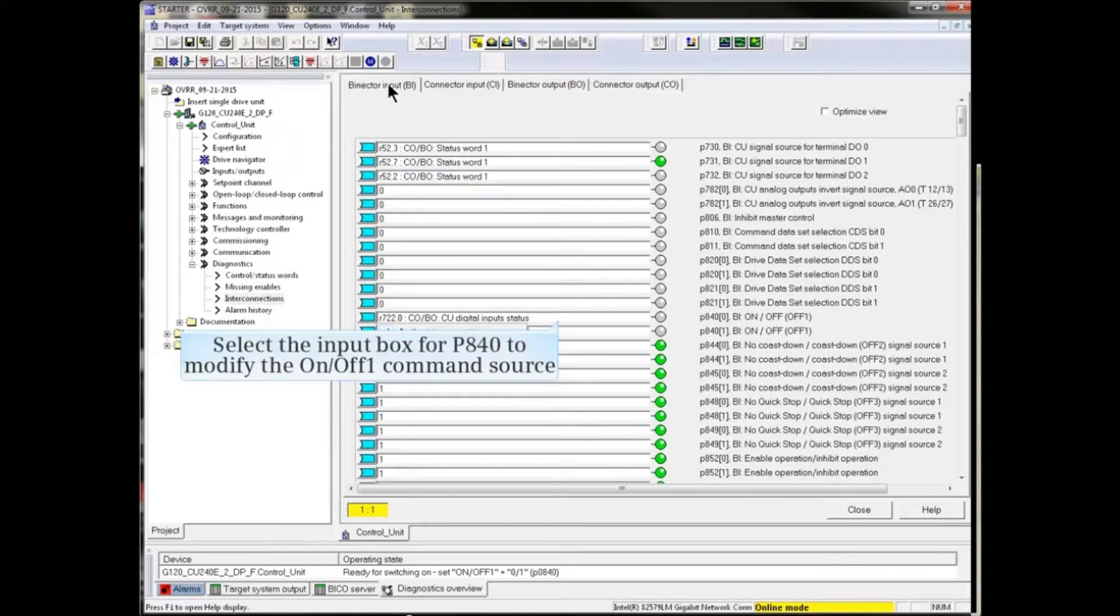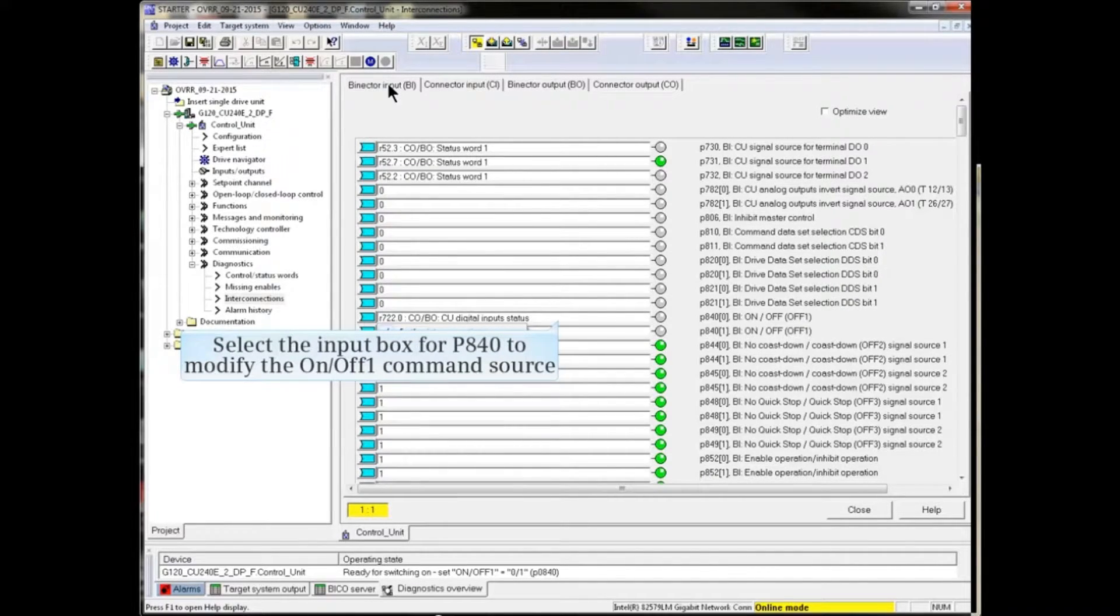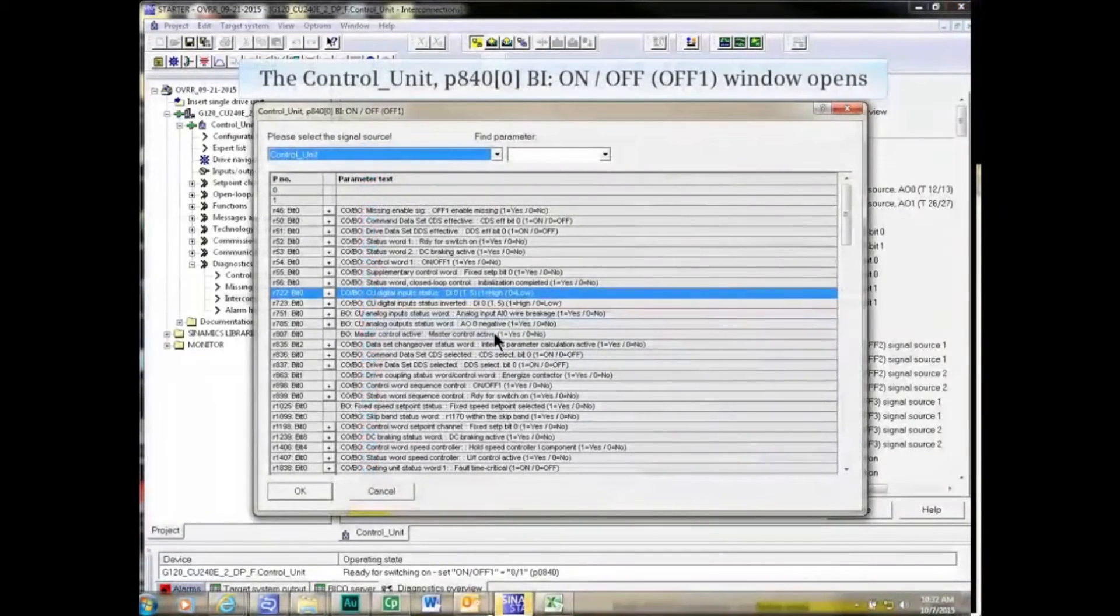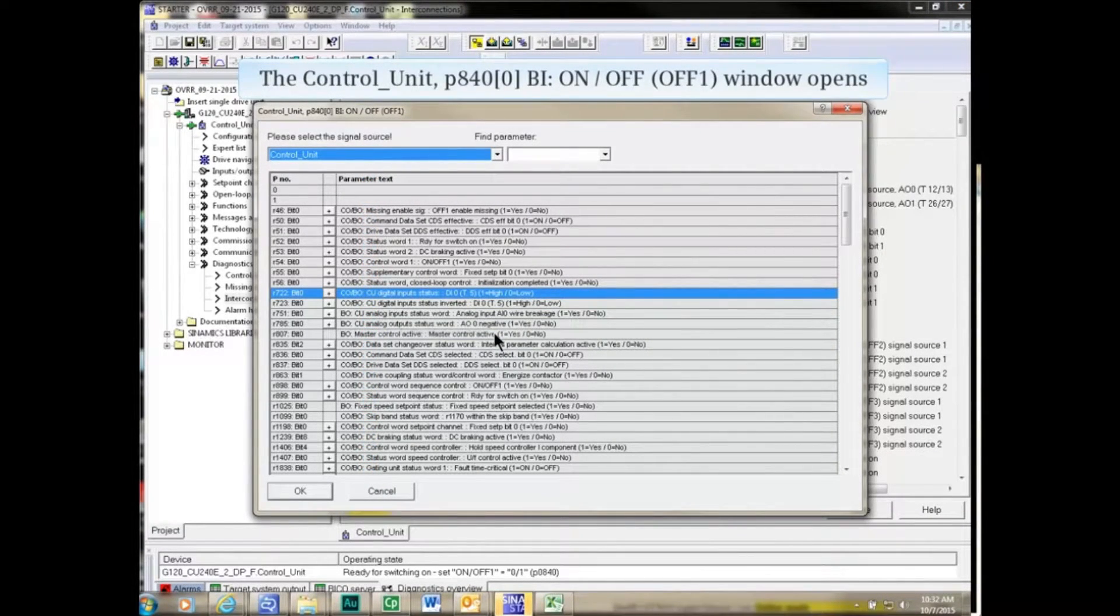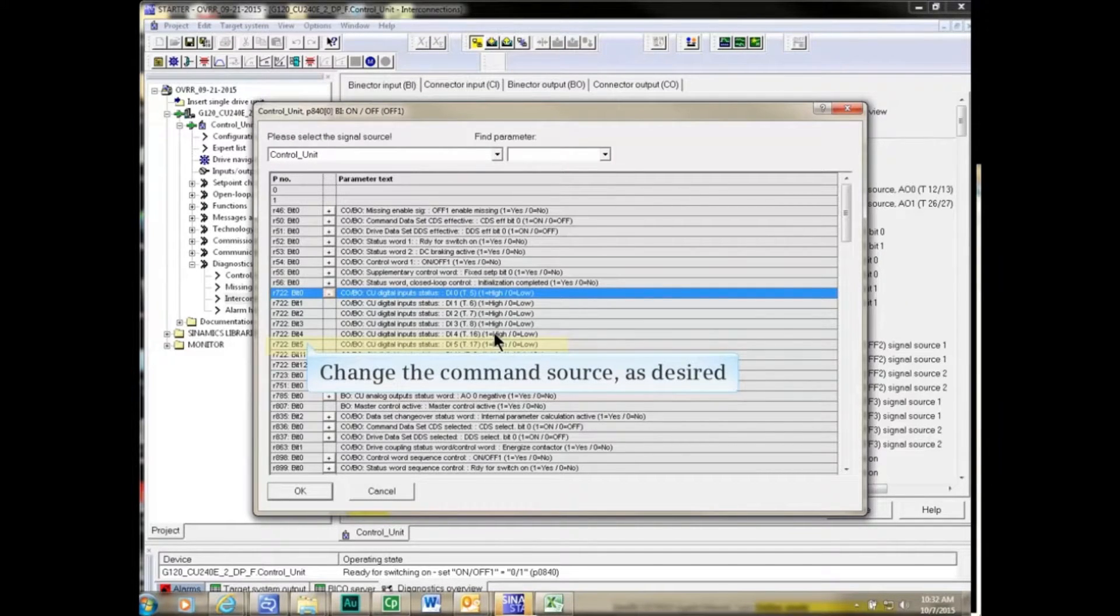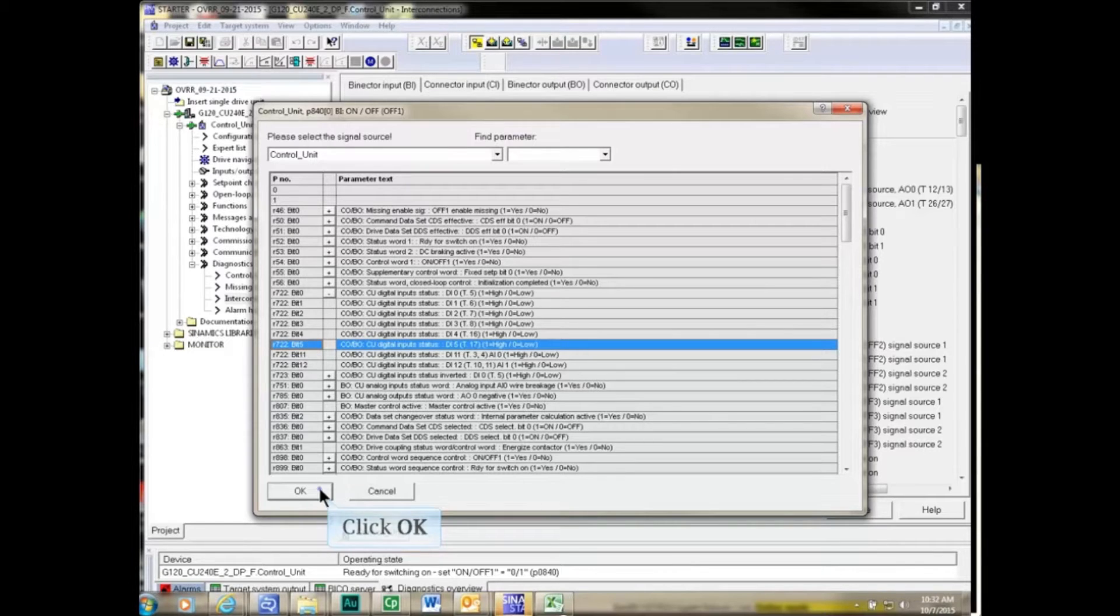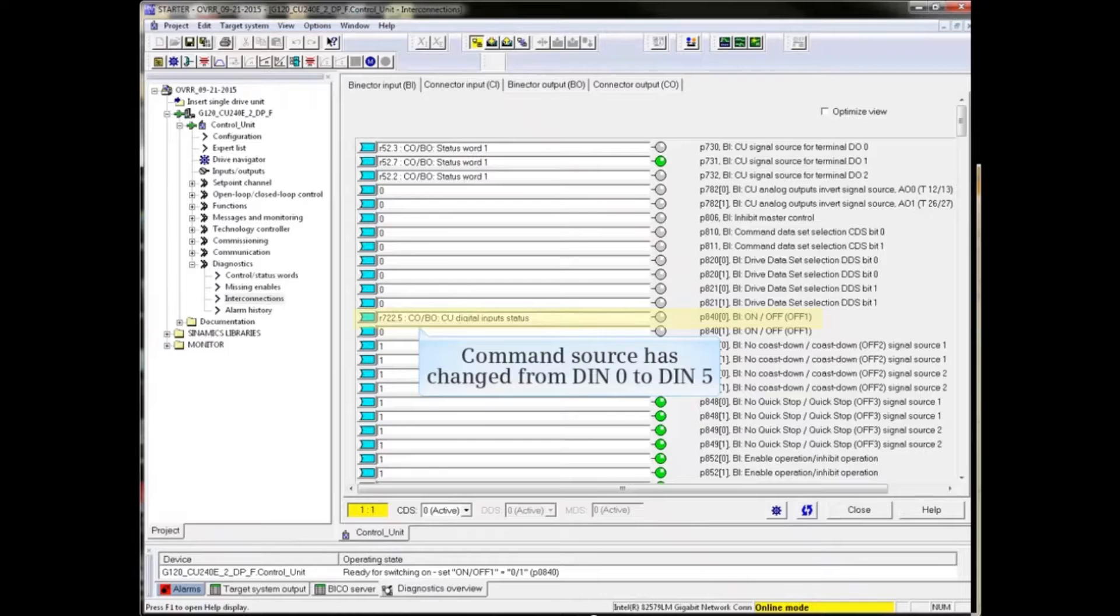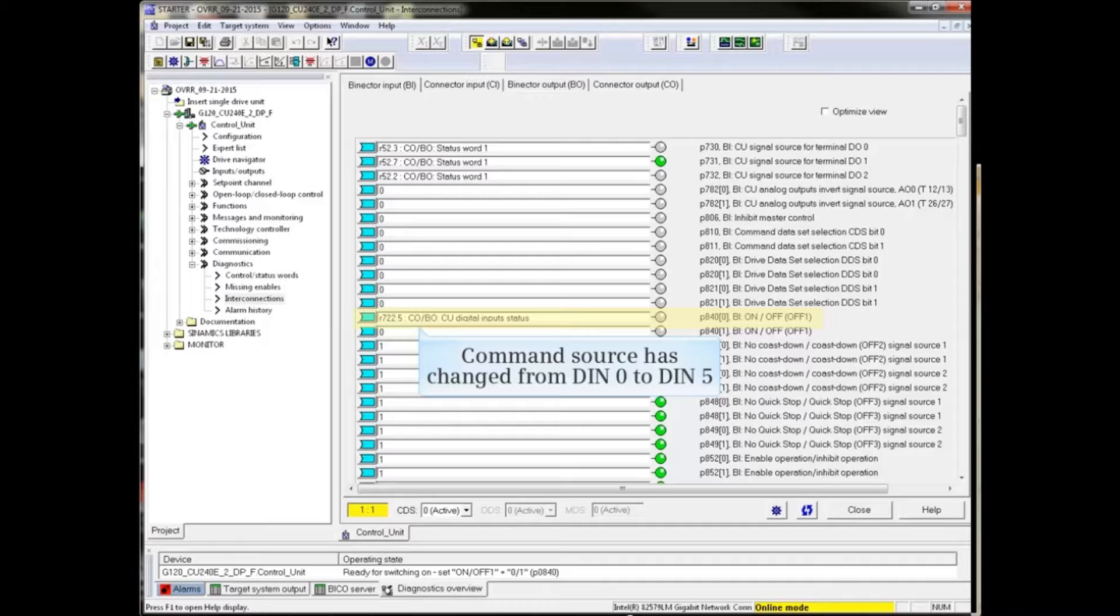To modify the ON OFF1 command source, click in the input box and select Further Interconnections. The Further Interconnections input window opens. Make the required change and click OK. In the example, the command source for ON OFF1 has changed from Digital Input 0 to Digital Input 5.